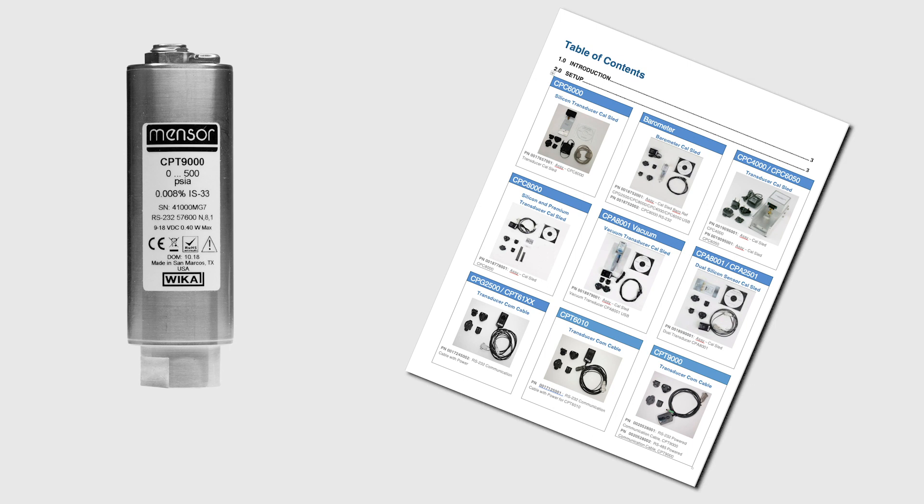This video will focus on how to calibrate the zero and span of a 500 PSI CPT 9000 absolute transducer. If points in between zero and span are required, refer to the linearization correction section of the manual.